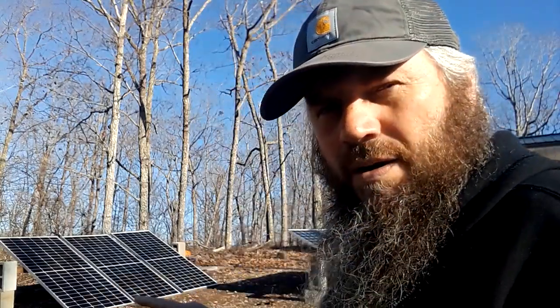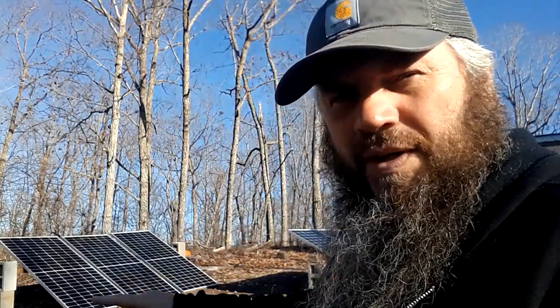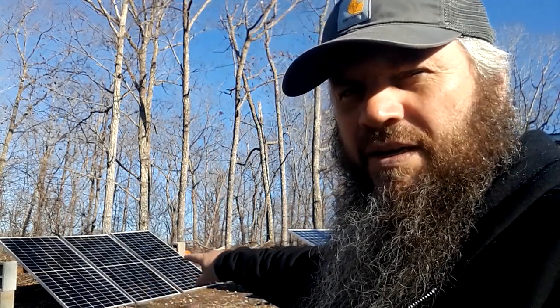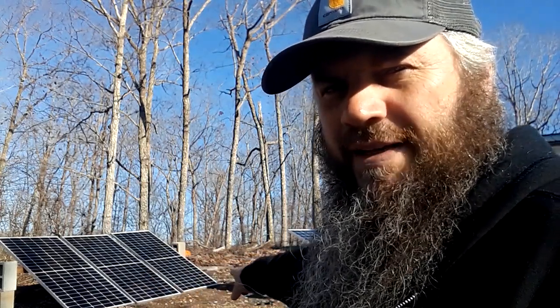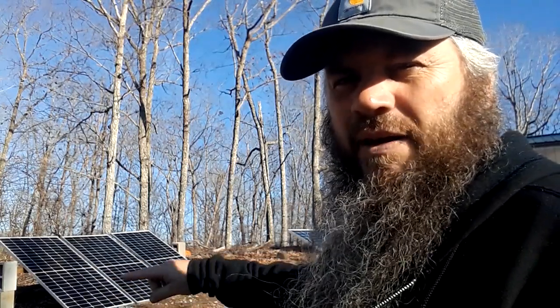On our solar arrays, the ones hooked in series here, each panel has a positive on one side and a negative on the other. Each panel is hooked in series to each other, positive to negative, positive to negative. We have one hot out and one negative out. What that does for us is it raises the panel voltage up, but keeps those amps pretty low.